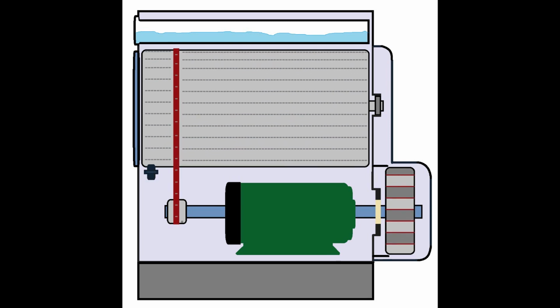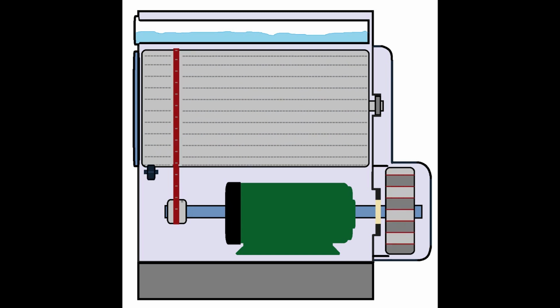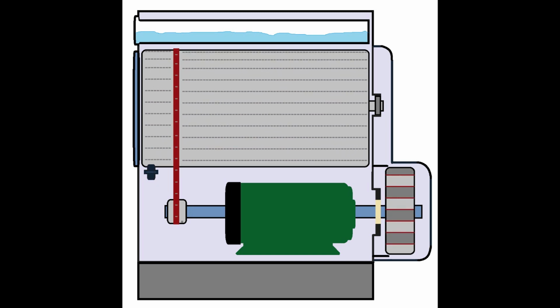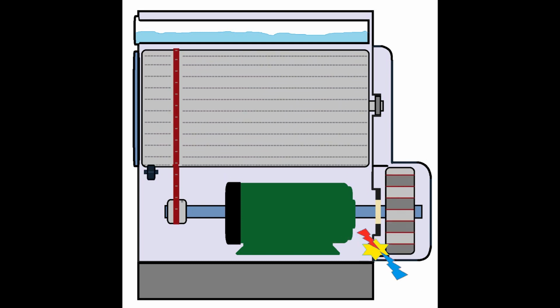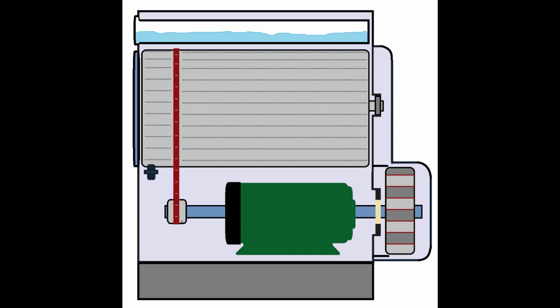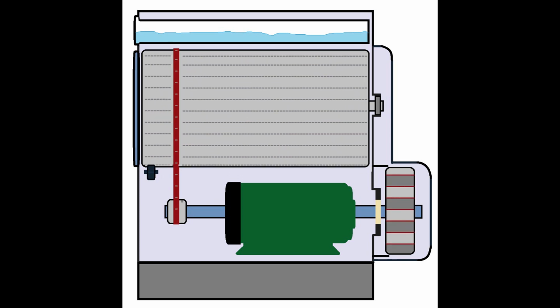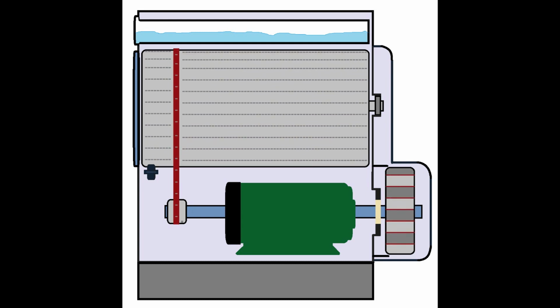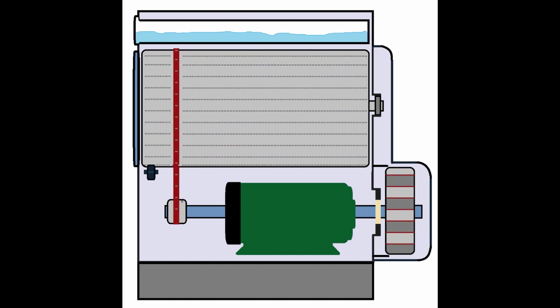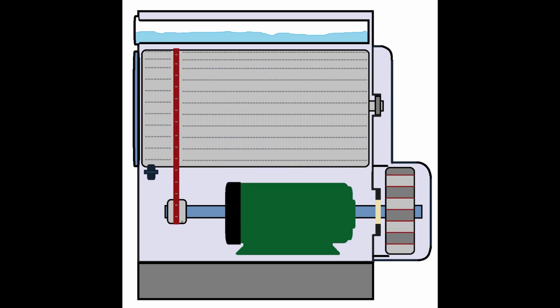Another fault can develop, and that's not your fault. If you see on the right hand side where the fan is spinning, that bearing sits on a rubber ring, and that rubber ring is getting old, and the fan is unbalanced and it starts touching the body of the machine, and that scroll could be damaged, or in my case it welded with the machine's body because it was plastic, so I couldn't start. When I started the system, I could hear the motor buzzing, and I had to use a knife to undo it and to change the ring. So I freed the fan to spin.